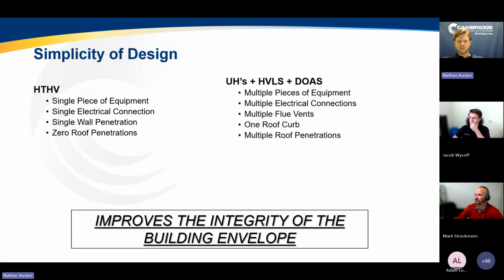So what this really gets at, other than value for money, is simplicity of design. When we're trying to develop a solution for a customer, the key thing we want to deliver is the most simple design that meets their requirements. There are a lot of benefits to this. You get a single piece of equipment versus multiple pieces of equipment, a single electrical connection versus multiple electrical connections. You've got a single wall penetration, potentially zero roof penetrations, depending on mounting configuration. And as you look at this, it really gets at improving the integrity of the building envelope.